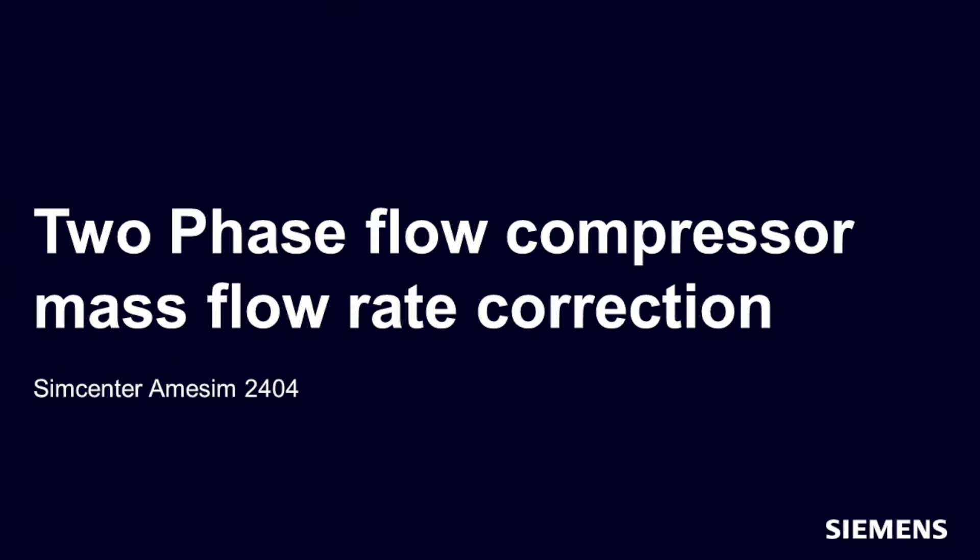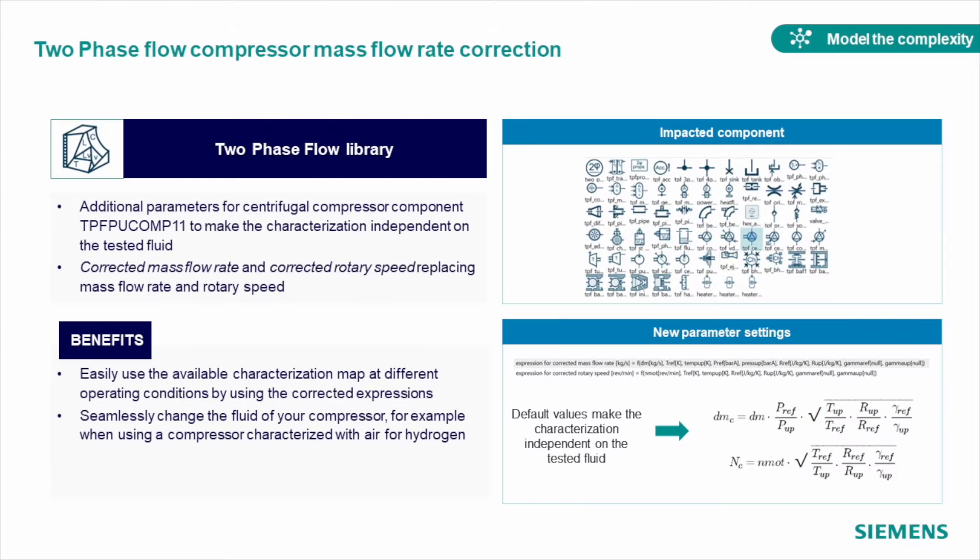In the newest release, we introduced corrected mass flow rate and corrected rotary speed in our compressor model from the two-phase flow library. This allows you to characterize your compressor independently from the test fluid with which, for example, the component was tested in documentation you have, and use it in the model with your own fluid to analyze how it works for the exact system you have.